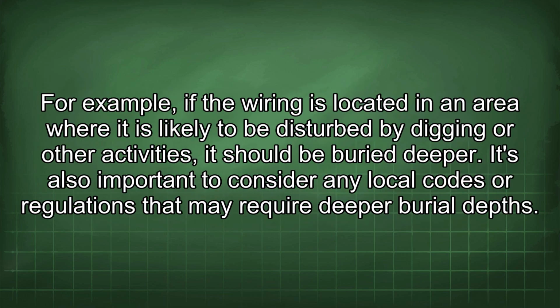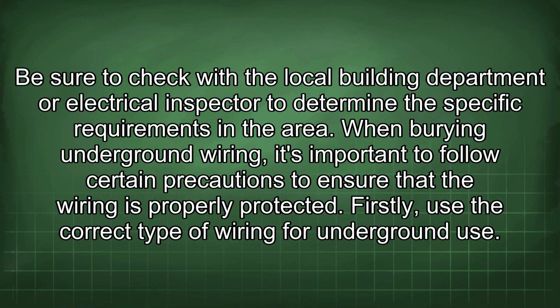For example, if the wiring is located in an area where it is likely to be disturbed by digging or other activities, it should be buried deeper. It's also important to consider any local codes or regulations that may require deeper burial depths. Be sure to check with the local building department or electrical inspector to determine the specific requirements in the area. When burying underground wiring, it's important to follow certain precautions to ensure that the wiring is properly protected.